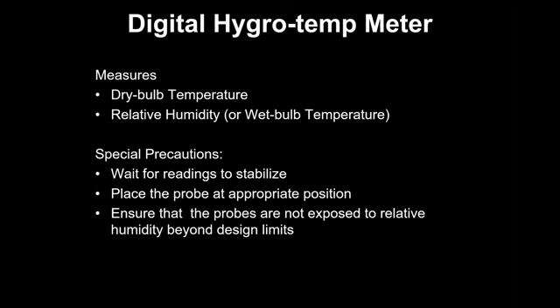This is another instrument that is used extensively, especially when you are doing HVAC studies for offices and textile industries. It measures dry bulb temperature, that's the temperature as it is, and it measures relative humidity or wet bulb temperature. So relative humidity is the humidity with respect to saturation, and based on that we do calculations on performance of the HVAC system, the hall condition, the comfort level, and all those things. So this is also a very simple instrument that way, not very expensive.